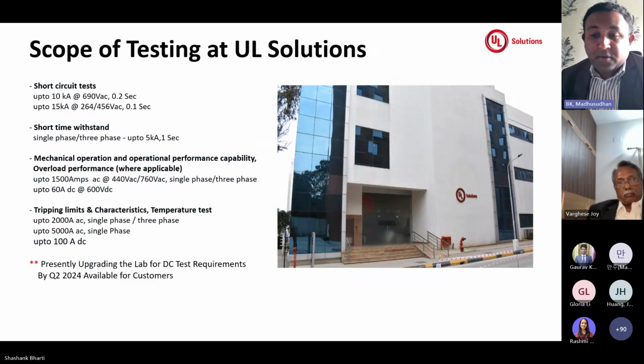Yeah, coming back to the scope of facility available at UL Solutions for this category of products. Basically, we have a short circuit lab in Bangalore with a capacity of 15 kiloamps AC to test all the breaking capacity tests here. We can go up to 690 volt AC for 10 kiloamps and 456 volt AC for 15 kiloamps, followed by a short time withstand current up to 5 kiloamps for 1 second. So any declaration under this range, we can take up the testing to complete your series.